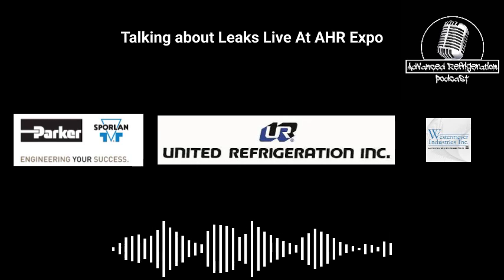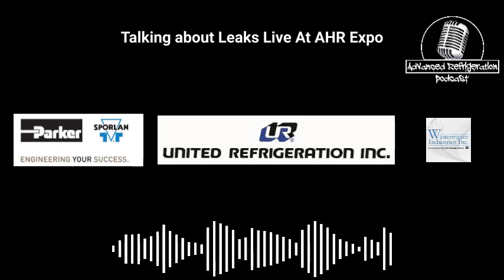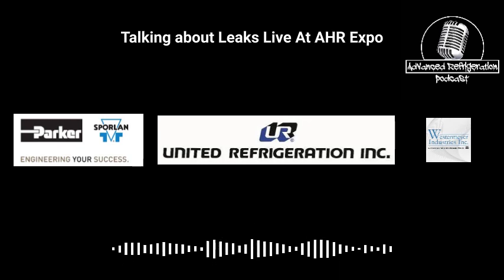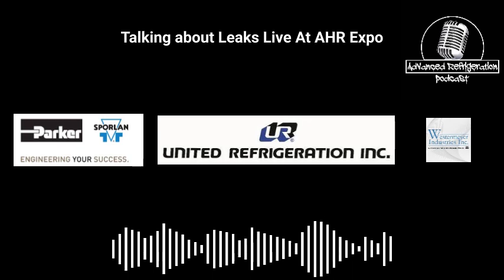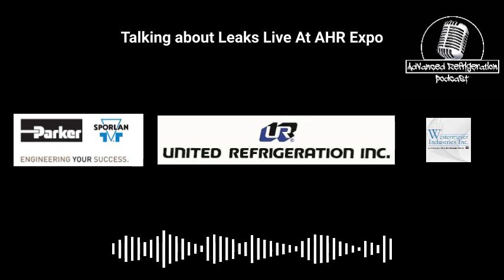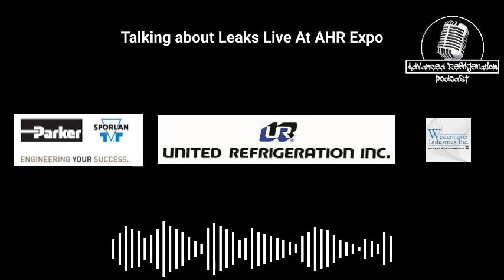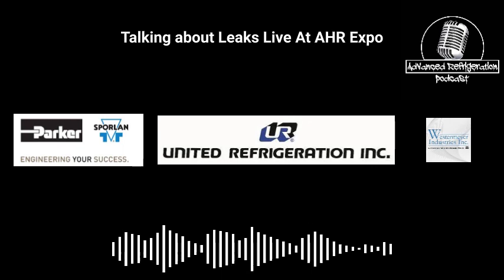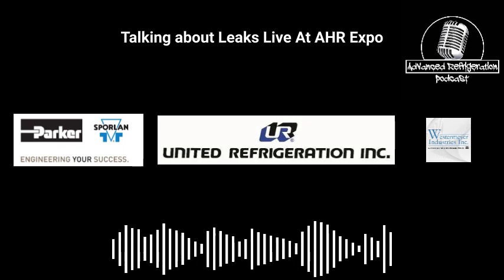I've seen way too many guys go put them on after they pulled vacuums, and then they have small leaks everywhere. You hear that, Andre? I told you, pressure transducers. A guy called me up the other day. He's like, man, I've been pulling on this rack for almost 2 weeks. Now, I don't know how big the rack is. I mean, Andre works on industrial. For the most part, he works on ammonia, but occasionally they've been doing a lot of CO2 starting up here. And he called me up. He's like, yeah, I'm only at like 14,000 and they haven't found a leak yet.